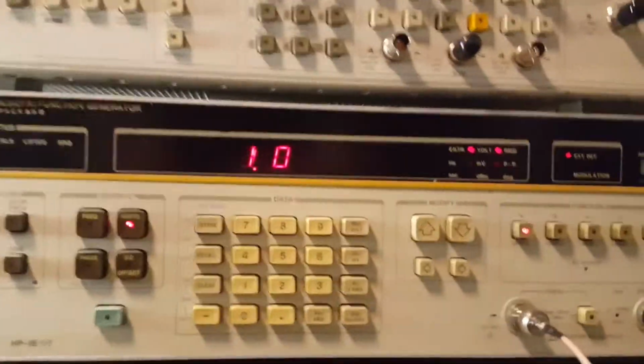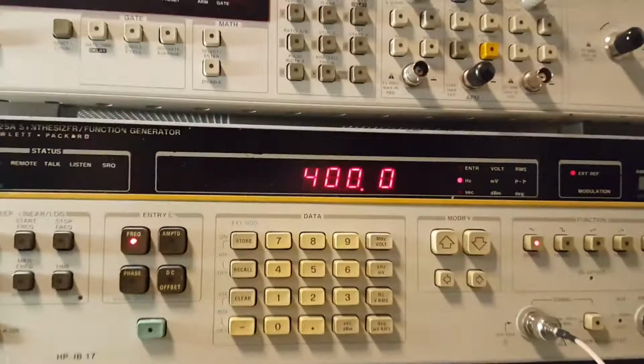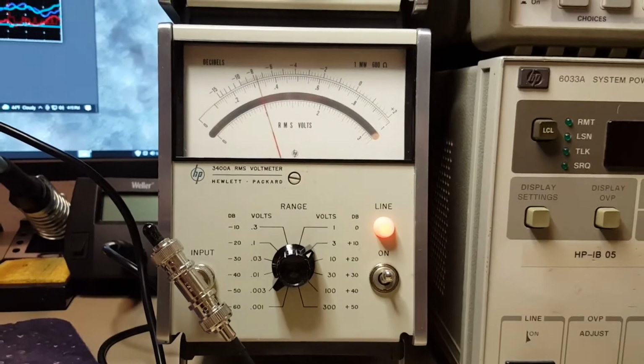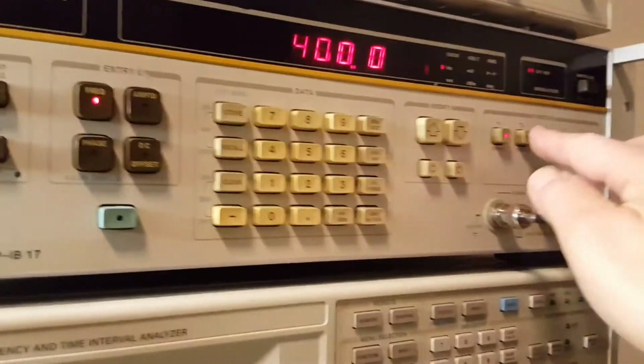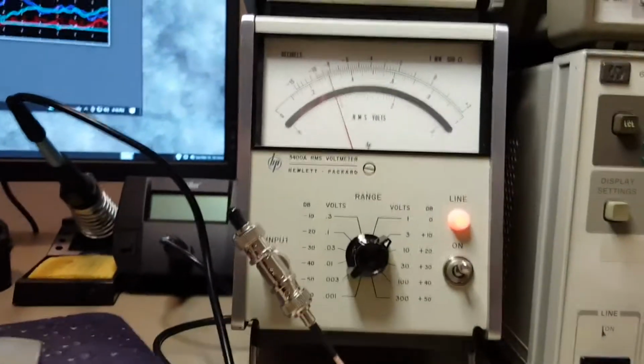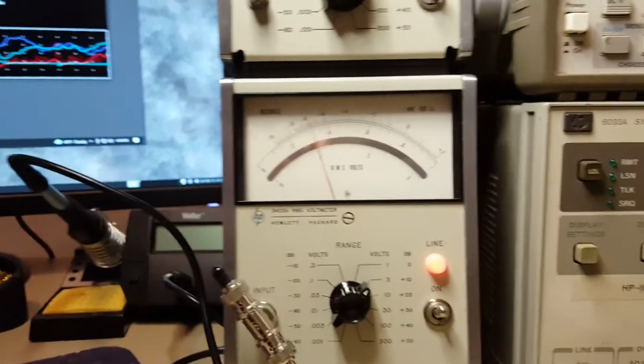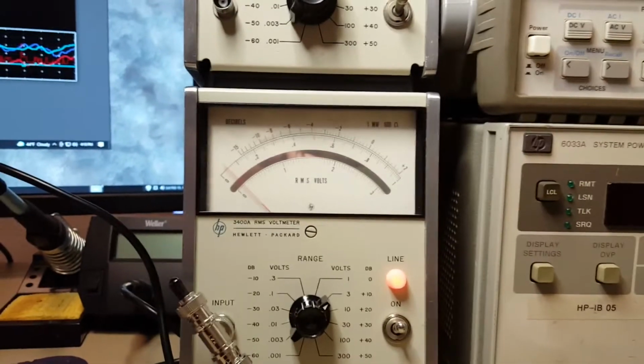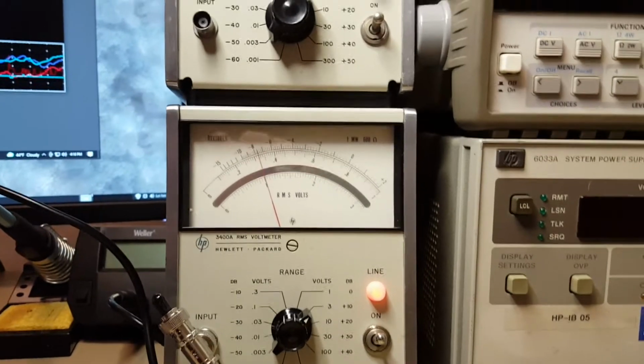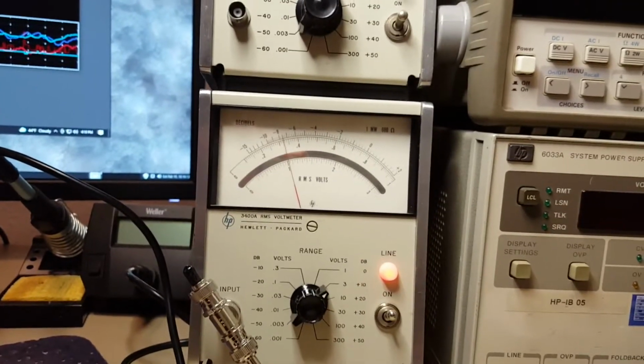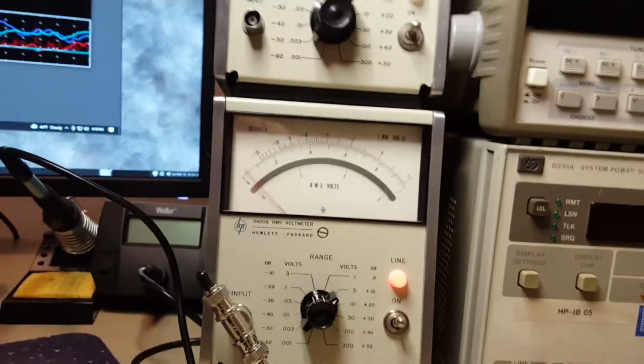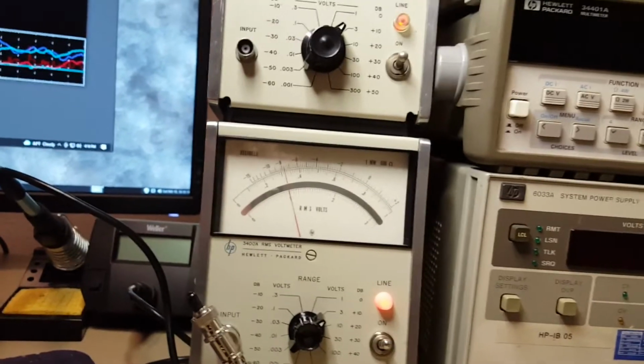So the parameters of this test, we're just going to demonstrate the meter's functionality. We're using a 1 volt RMS output at 400 Hz. And the meter is showing 1 volt RMS. Now I can change the wave shape. We can go to square wave, and it shows 1 volt. I can change it to triangle, and it shows 1 volt. Positive ramp, same thing. Now we'll go back to sinusoid, and it's on the money.